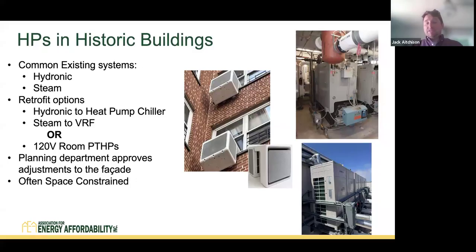For steam systems, it's a little bit harder. There is no drop-in replacement steam heat pump water heater. And so your options are a variable refrigerant flow heat pump, which Scott touched on a bit, but this is basically a commercial heat pump HVAC system that sends refrigerant all throughout the building. The variable refrigerant piece allows you to heat one zone and cool another zone, which is great. We often see these in commercial systems, but it's a pretty costly retrofit. It's going to require a lot of refrigerant piping. You're probably going to be opening up walls.